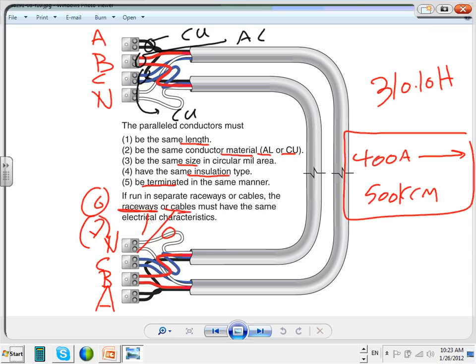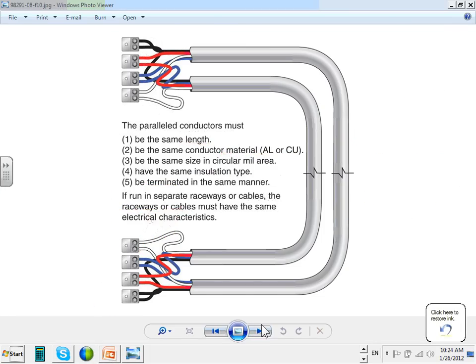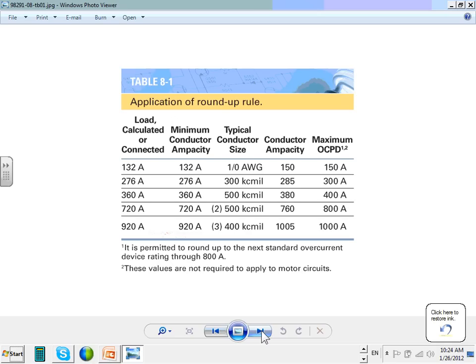The only thing you need to pay attention to is that the lugs have to be rated for aluminum at the end, because the phase A conductor and phase B conductor are not parallel. So I wouldn't do that. Only the phase conductors must be parallel. Must be the same material? Yes, the same material, the same phase or the same neutral. Okay, any questions about this? Hopefully that picture brought the parallel home to you. When do you parallel, and when do you use parallel, and so forth?